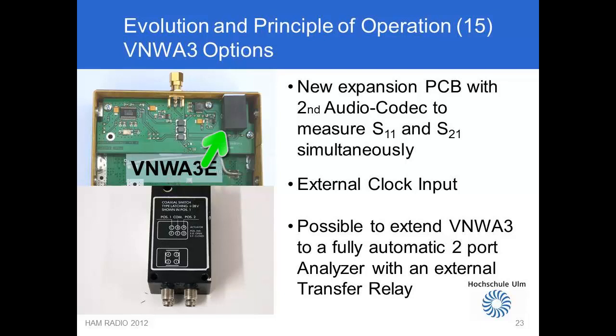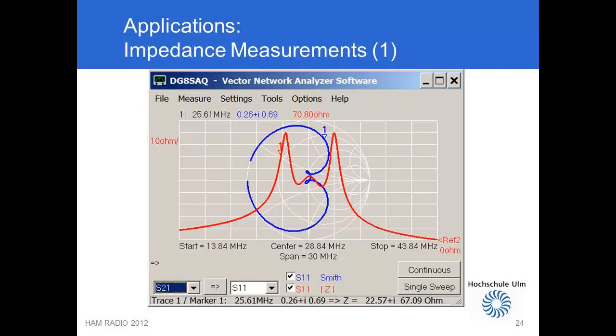Top right is an RJ12 connector for outside world connections, where you, as an example, can connect a transfer relay or a homemade test set for automatic measurements of all 4 S parameters of a 2-port device, such that it is not needed to mechanically turn the device under test for reverse measurements. It is also possible to connect an external reference signal for improved accuracy. More on this later. Let's look at application examples.